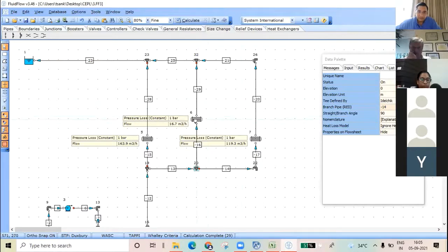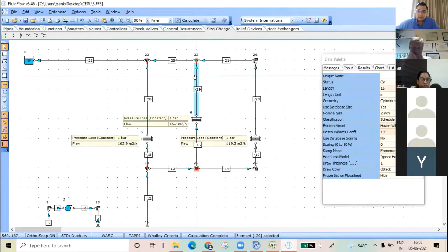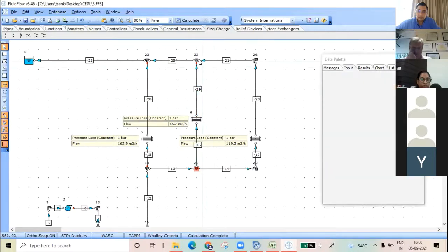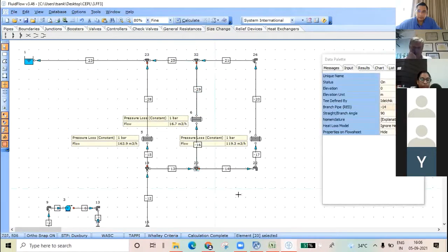Now this one is having less flow. Why is there more delta P in this line? So second heat exchanger T, inlet side. Okay. Flow is going properly at 1, 2, 3, 4 places. Okay.